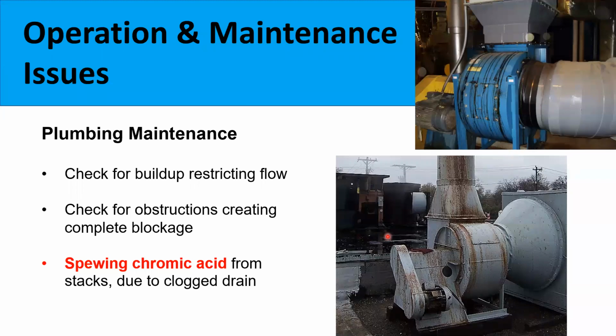Another kind of nasty issue that occurs is blockage in a drain system on a wet scrubber that can ultimately lead to bypass and ingestion of a chemical into the fan. What happened is what occurred here in this picture. This is a chromic acid solution that was operating on a dry composite mesh pad system that also had a wet section along with it, prior to the MACT standard, which moved all compliance to a dry mesh type system.